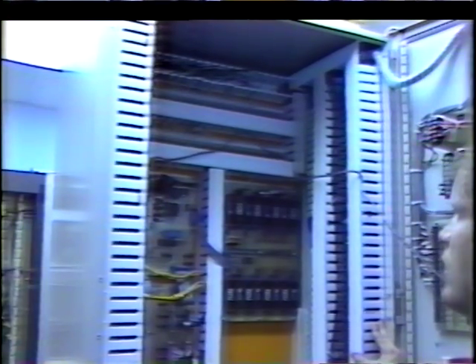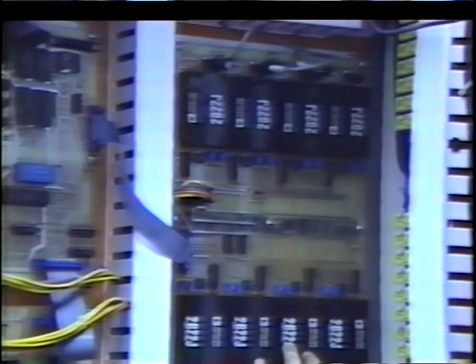On the internals of the Williams System 200 control system, you will find a 3-board set of computers. The board on your right of the cabinet with the 8 large black modules on it are your analog output. These analog outputs control the spinner speed, feeder speed, and mill speed at this time. You then also have 5 spare control signals for other devices in the plant if need be.